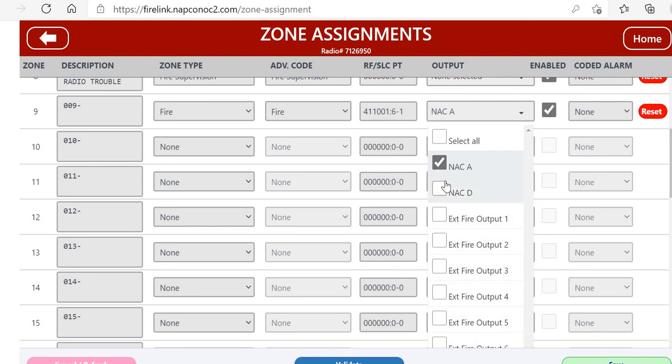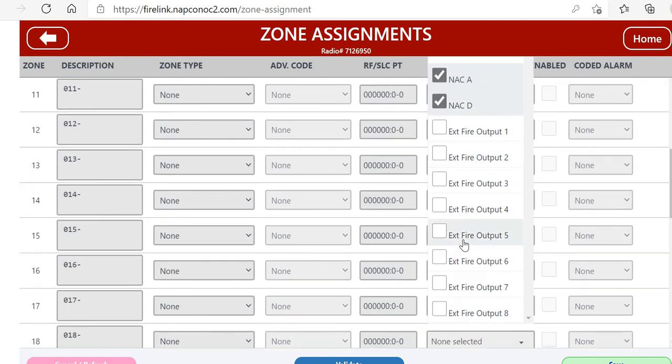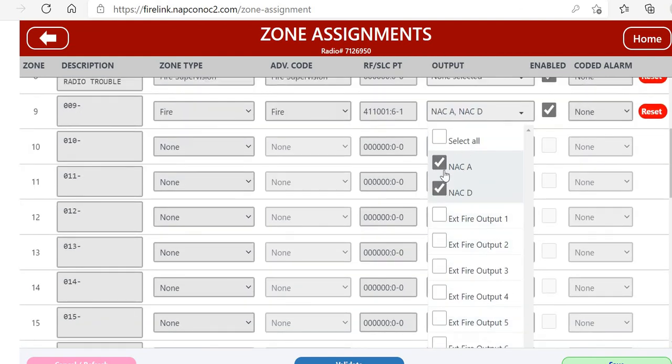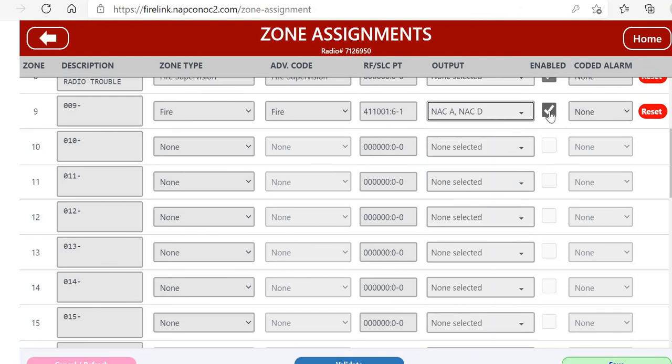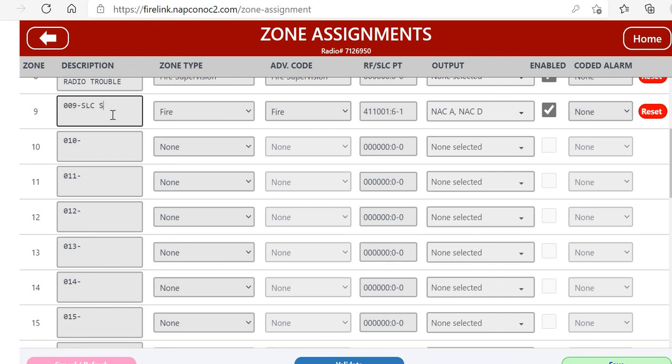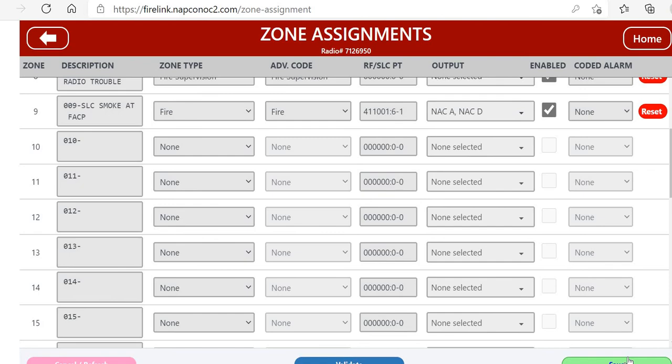Now we can go over to the output section and this is where we can pick what NAC or NACs - NAC A and D - or an external fire output that we want on the zone. We're going to click enable so the zone is in the system. If we were doing coded, that's where you would pick that, and we can also give it a description.